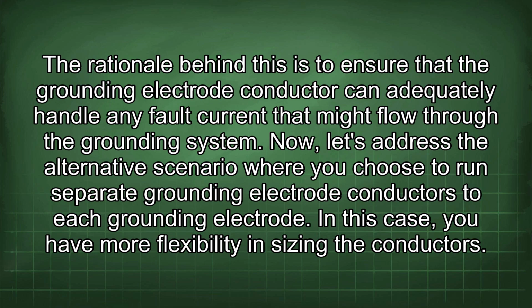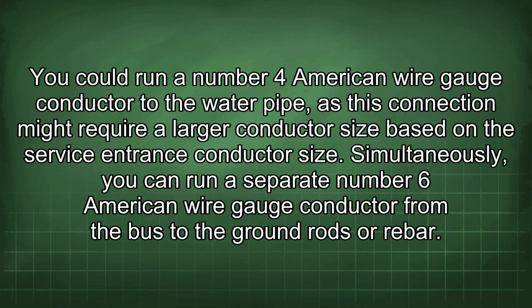Now let's address the alternative scenario where you choose to run separate grounding electrode conductors to each grounding electrode. In this case, you have more flexibility in sizing the conductors. You could run a number 4 American wire gauge conductor to the water pipe, as this connection might require a larger conductor size based on the service entrance conductor size. Simultaneously, you can run a separate number 6 American wire gauge conductor from the bus to the ground rods or rebar.